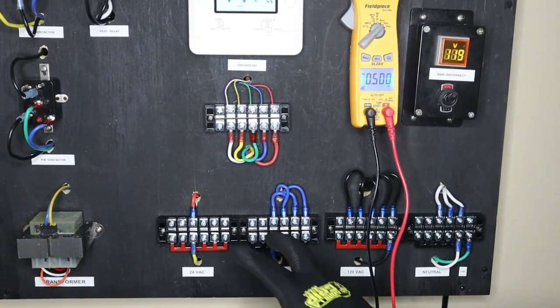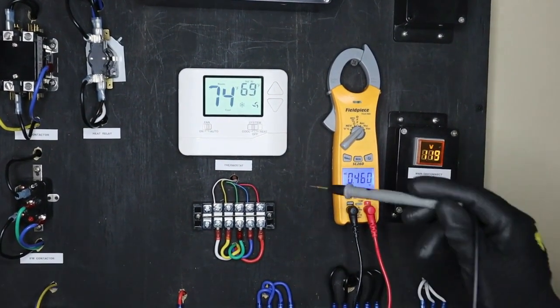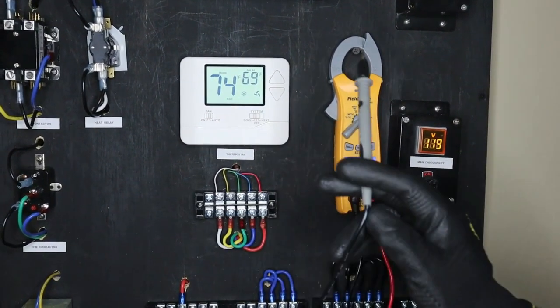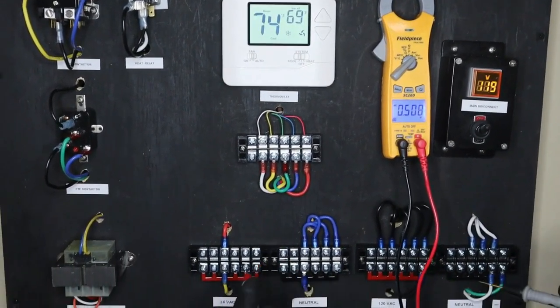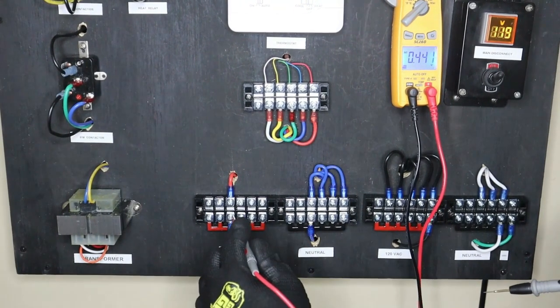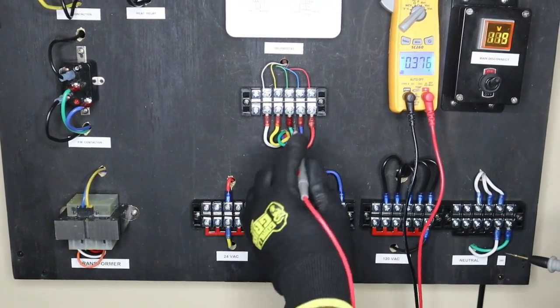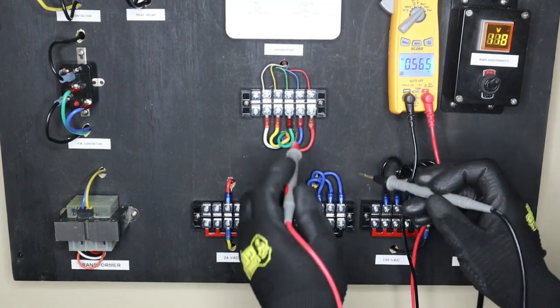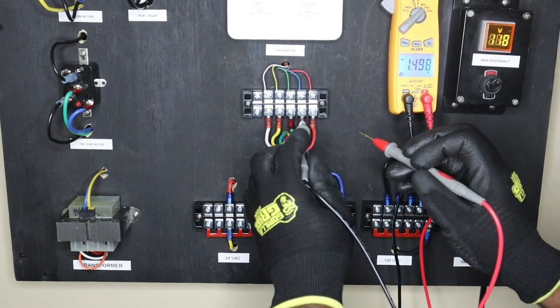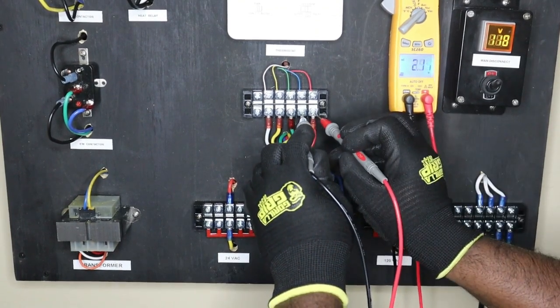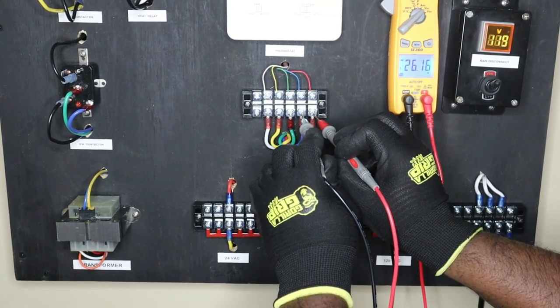Now this low voltage AC then feeds to my thermostat which then distributes the low voltage power to all my contactors and relays in my system. So as you can see my 24 volts comes into this terminal block. My red is my 24 volts, my blue is my neutral, and I should measure my terminal block leading to my thermostat. I'm measuring 26 volts.